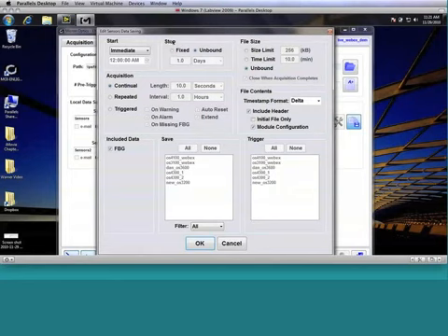Similarly, we have controls on when that data logging event stops, and this is basically the entire data logging event, independent of whether it's continuous or repeated or triggered. So this is basically for the entire data saving profile. On Unbound, it will continue to record until such a time as you, the user, go in and disable the button, the start data logging, stop data logging button. Alternately, you can establish a duration for your data logging event in units of seconds, minutes, hours, or days. So again, in our very simple example, we'll be Unbound where we just start and stop.